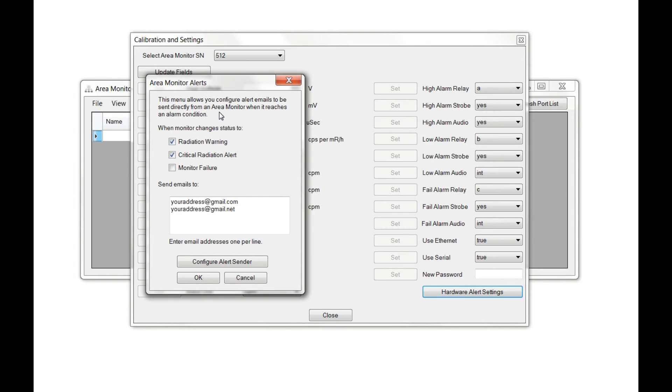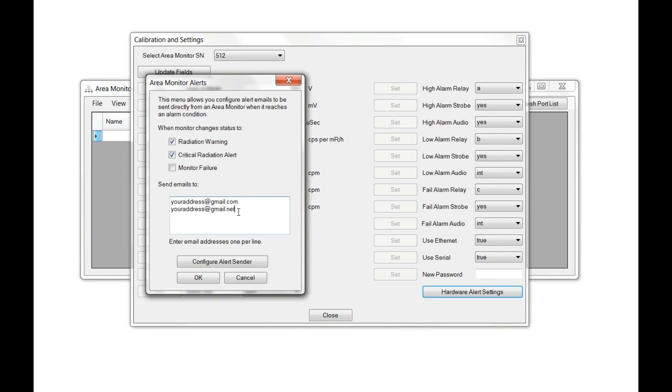Unlike software alarms, you can only set up a single alert should a warning or critical radiation alert happen. However, you can send that alert to multiple email addresses. You can also send it via text using SMS. For more information on sending text via SMS, visit our website at seintl.com.